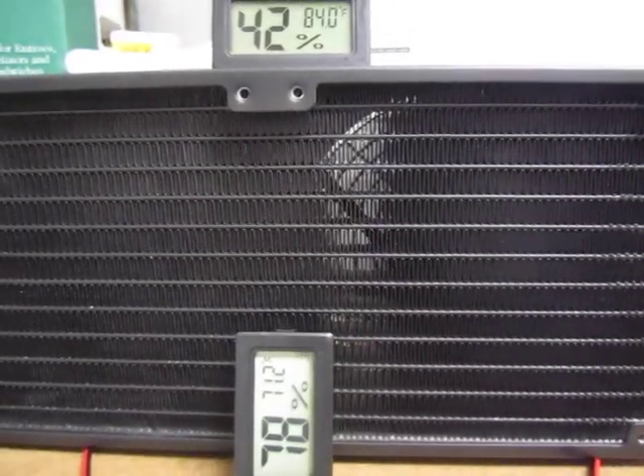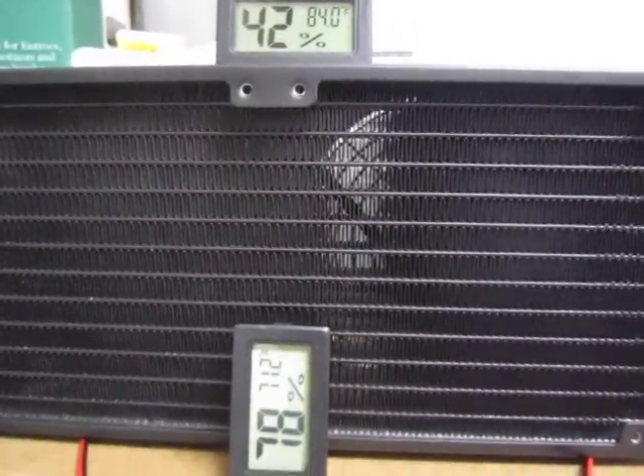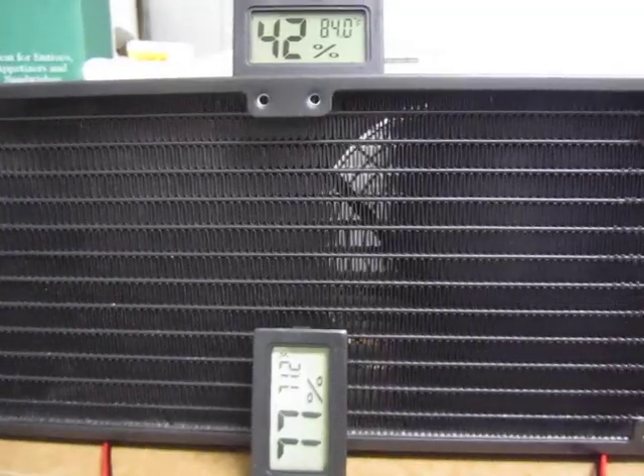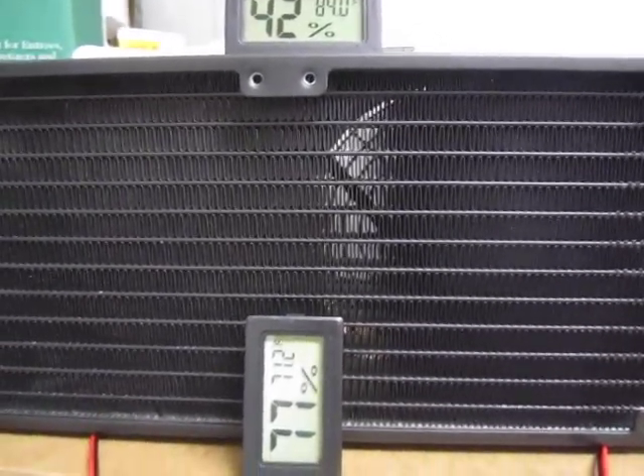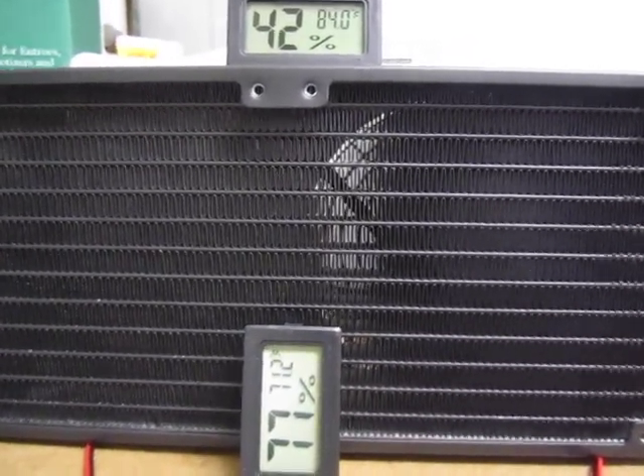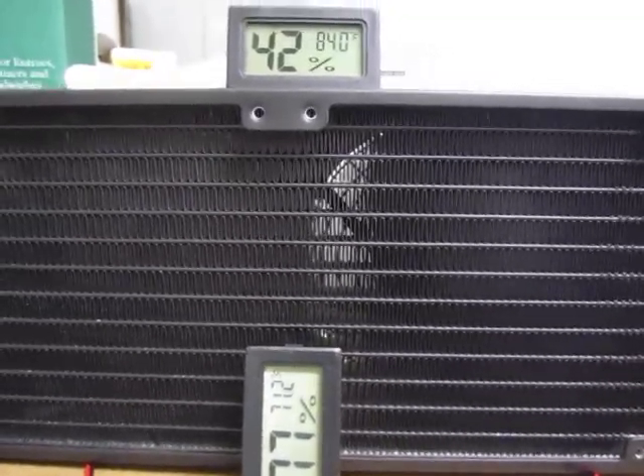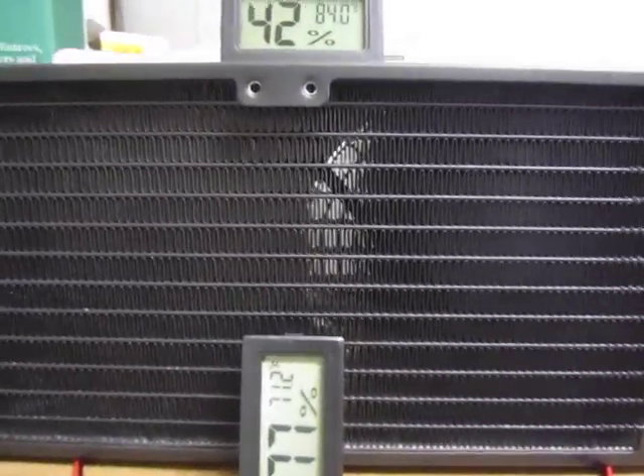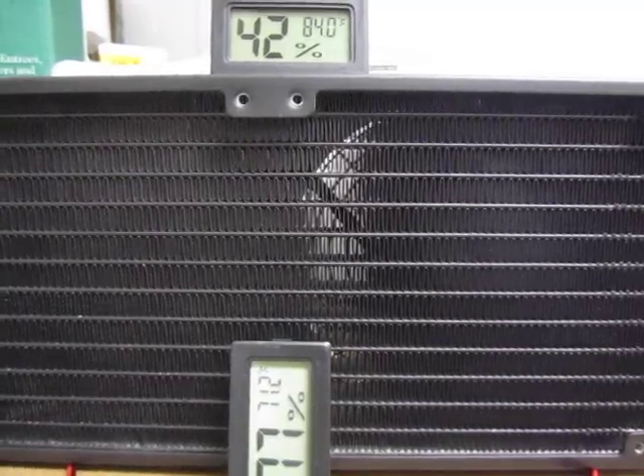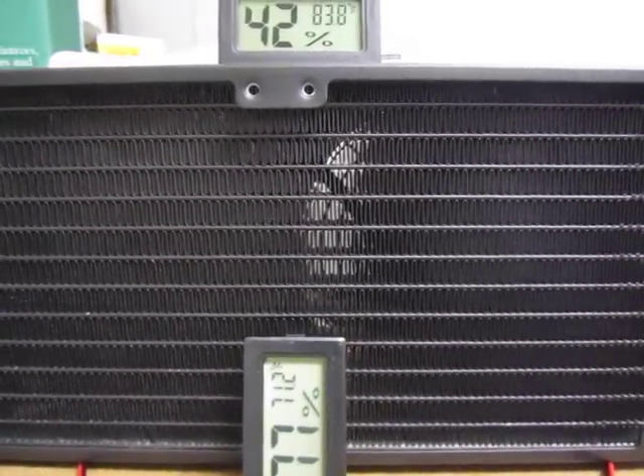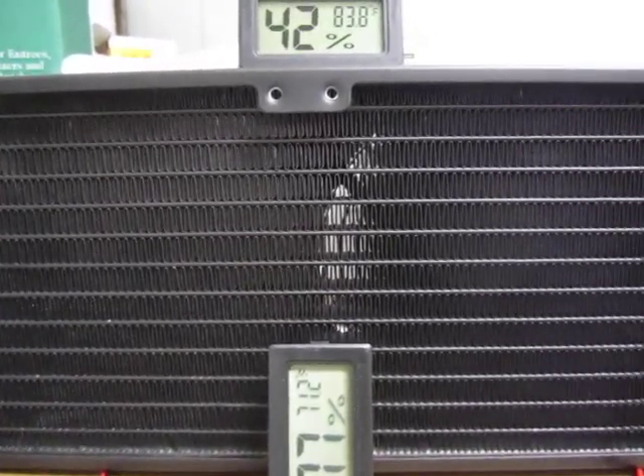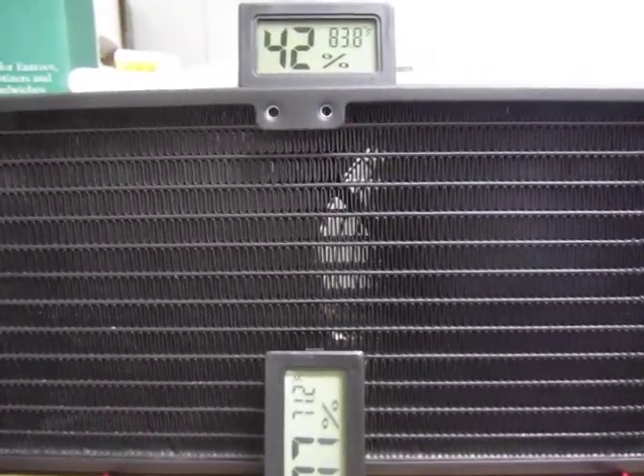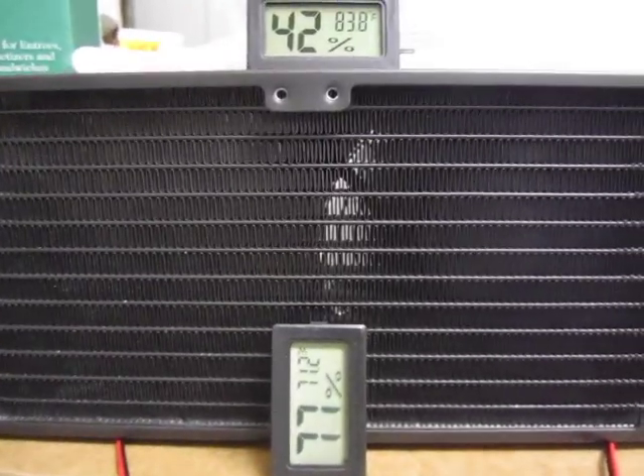So this is about 15 minutes later now, and as you'd expect, the temperature on the cold side has warmed up a little bit. It's only 71.2 degrees now, so this is still cooling, and still about a 10-degree temperature drop. But as we'd expect, the temperature is steadily increasing now, though we still have some cooling capacity left, so we're going to continue to let this run.